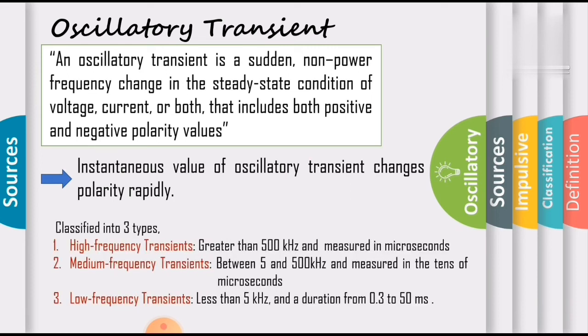Oscillatory transients are classified into three types: high frequency, medium frequency, and low frequency transients, divided according to their frequency levels. High frequency transients have frequency components greater than 500 kilohertz and a typical duration measured in microseconds — in the tens of microseconds. Low frequency transients have frequency components less than 5 kilohertz and a duration from 0.3 to 50 milliseconds.